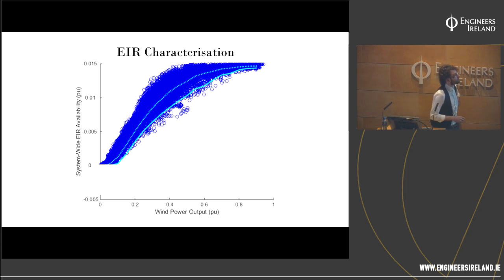The wind varies throughout the system, and in order to get a full handle on the potential for wind power to contribute to system stability, you need to be able to characterize how many wind turbines are online, because that's all that matters. For any sort of rotational machine to provide an inertial response, it has to be online. So for a wind turbine to be online, it has to be above its cut-in wind speed, but also because the controls will slow down the turbine to inject power, you have to be above more than your cut-in wind speed. You need roughly about 0.2 per unit of the wind turbine rating, so that when the machine does slow down, it doesn't stall. So generally, inertial controls will only be implemented above a certain wind power output.